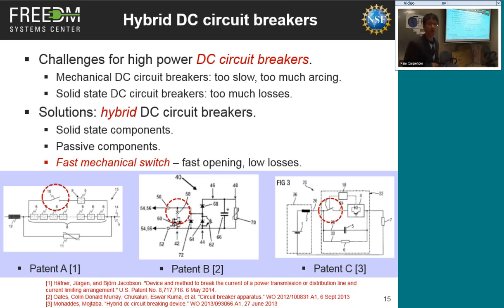There are a few ways to interrupt the DC circuit. As I mentioned, there can be mechanical DC circuit breakers. There can be solid state ones. I haven't talked much about that, but solid state means you use power semiconductors. There will be very high losses. So this loss is not that simple. It's loss in your system. You need cooling. That's extra cost. And you are actually stealing power from the transmission system. That's really a bad thing.